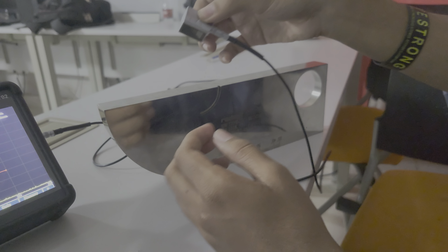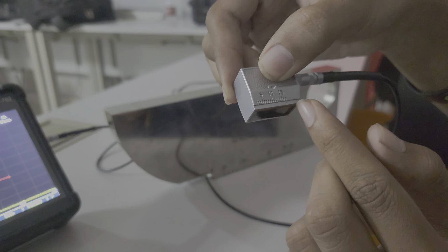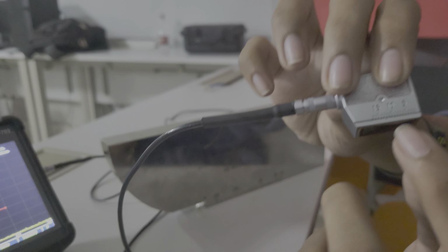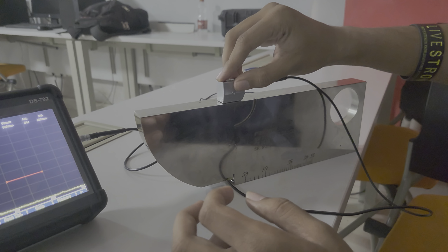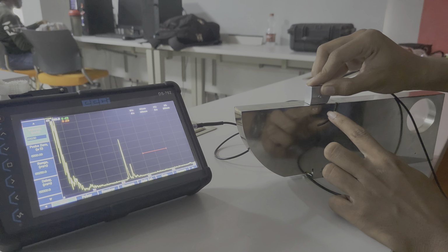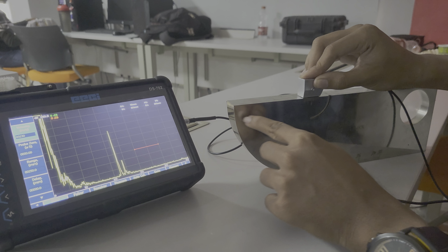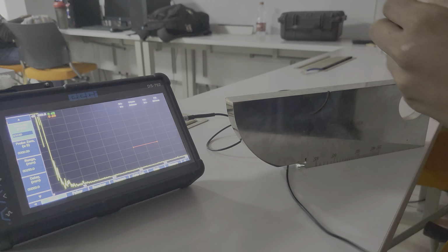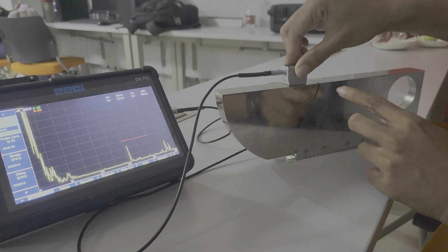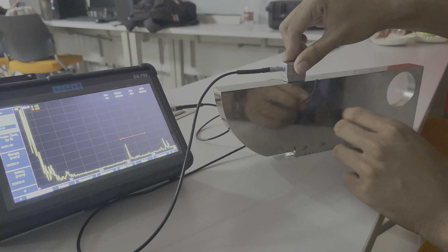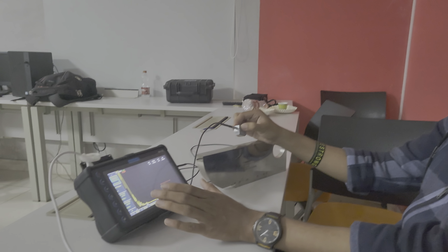As now we will place this, it also has 3 different dimensions, 5, 10, 15, and this one also has 15, 10, 5. That means if we are keeping our probe over this at the 10, the waves are transmitting this way in the 100 mm direction. But if we keep our angle probe like this, the waves are transmitting towards the 25 mm direction.